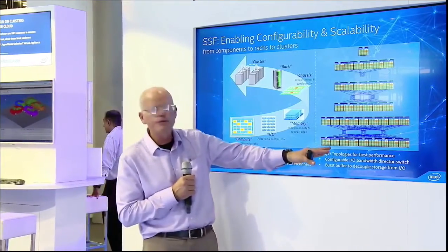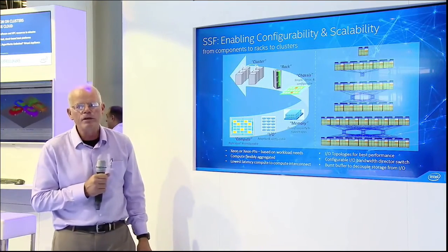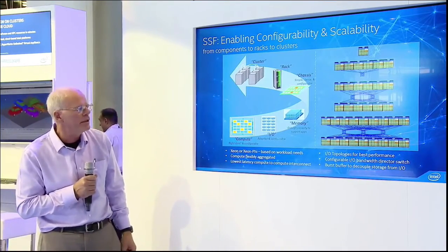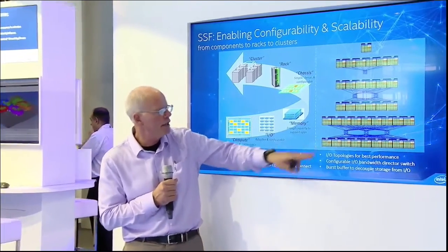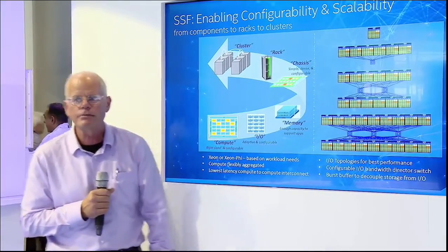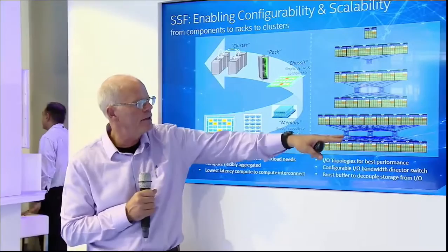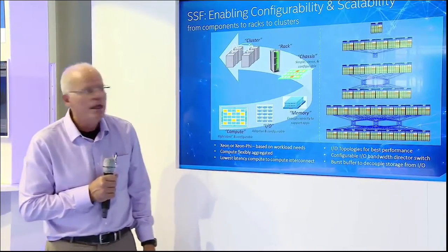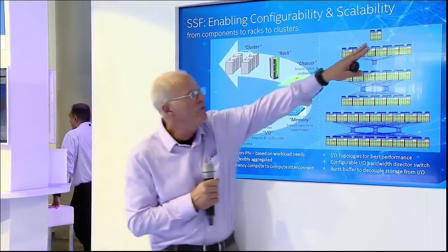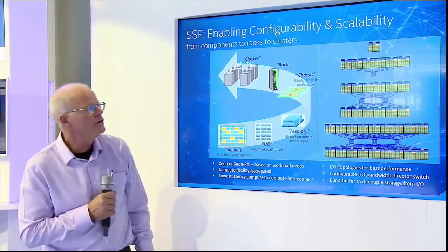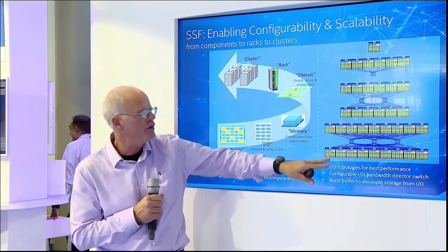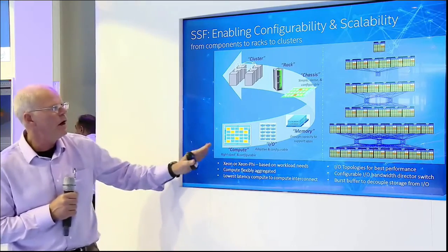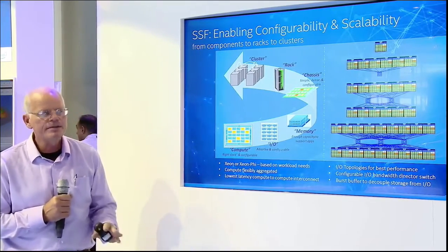So we have two basic approaches here. One is the traditional Beowulf COTS Linux cluster approach, where it's commodity off-the-shelf components put together in standard racks with air cooling in basically a fat tree interconnect where we define scalable units, and at the top of each rack in that scalable unit are top of rack switches that are the first stage of the interconnect, and then the second stage of the interconnect is a heavy duty spine switch that allows you to hook multiple scalable units together. In the KNL time frame, in 2016, we have a half a petaflop single scalable unit, and strapping 18 of those together with 3 spine switches with OmniPath 1, you can actually get to 10 petaflops very cost effectively.